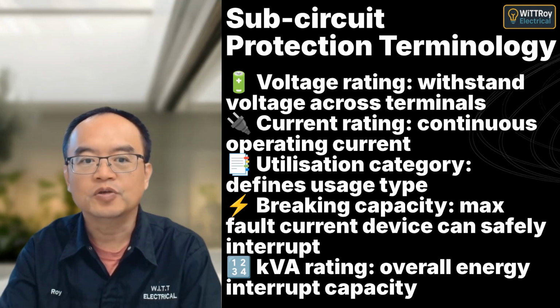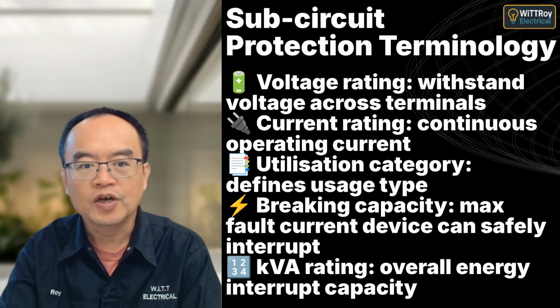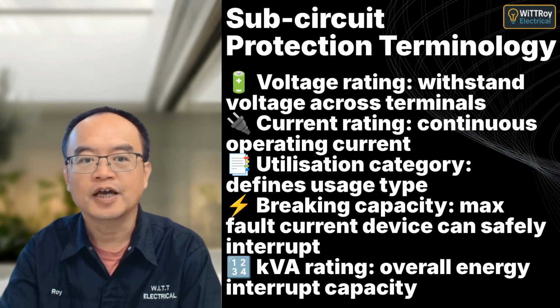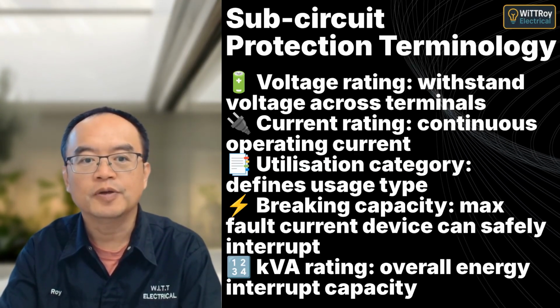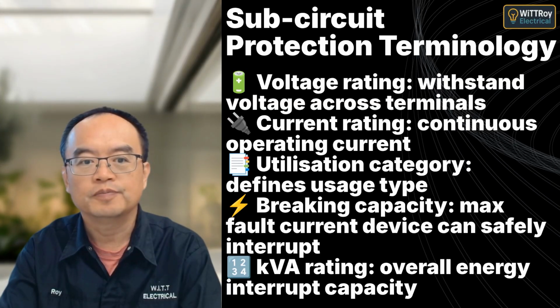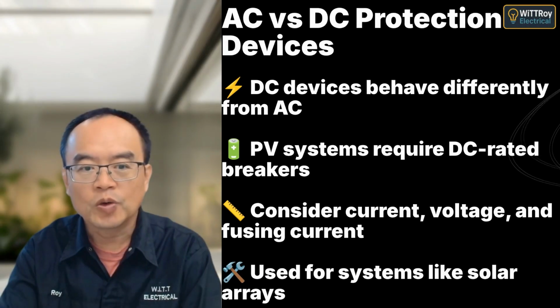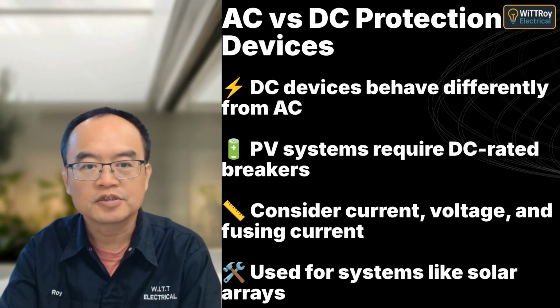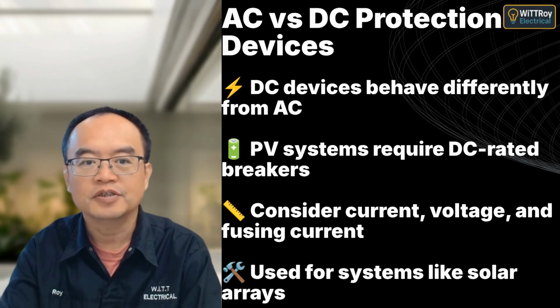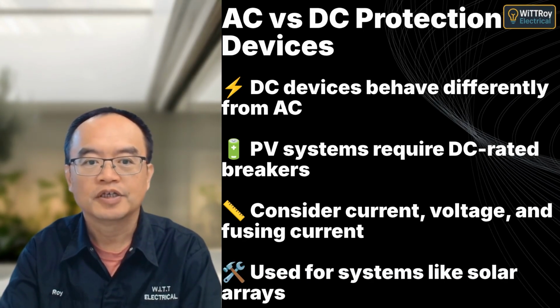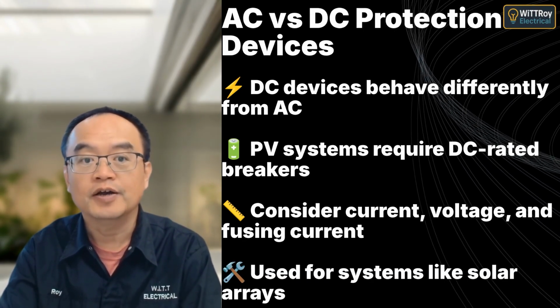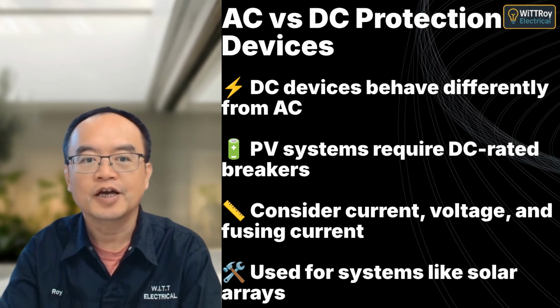Each term defines a critical performance limit of protective devices. The correct understanding helps ensure safe device selection, especially for sub-circuit protection. When working with photovoltaic or DC systems, use DC-rated protection devices. They handle continuous DC arcs and often have higher breaking capacities than their AC counterparts.